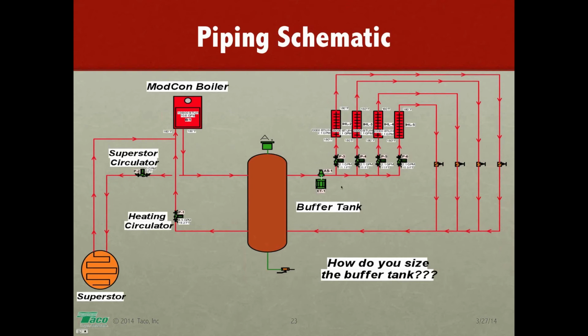Here's your schematic again, where you have your expansion tank and air separator. On your distribution side, here are your heating circulators, your heating zones, if you're zoning with circulators. Over here we have the boiler and our boiler circulator, as well as the indirect on the other side. Okay, so here's your basic piping schematic. It's the same piping schematic for a hydraulic separator.